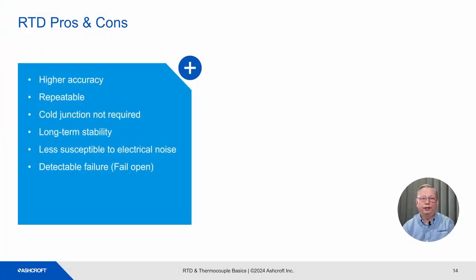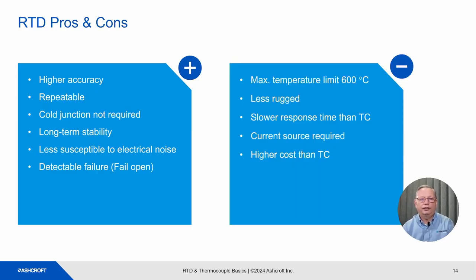Next is the pros and cons of RTD and thermocouples. RTD probes are higher accuracy than thermocouples, with better repeatability. They do not need cold junction compensation, and have better long-term stability. They are less susceptible to electrical noise, and they typically fail open, which can easily be detected. The cons are lower maximum temperature limits. They are less rugged than thermocouples. They have a slower response time. They do need a current source to have an output. They cost more than thermocouples.